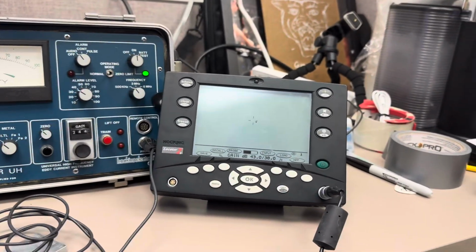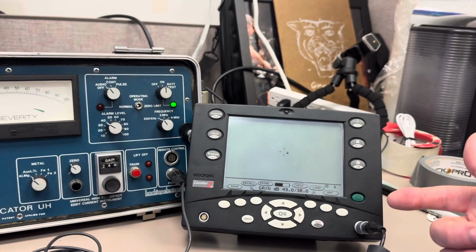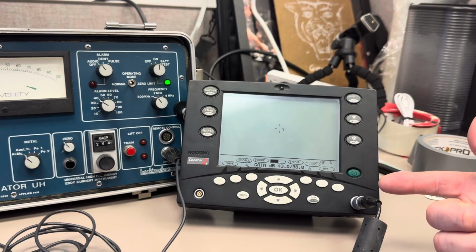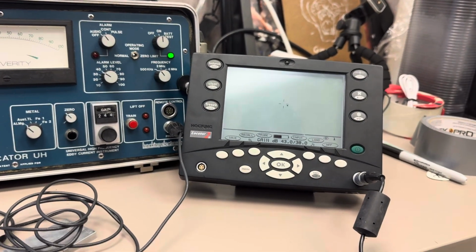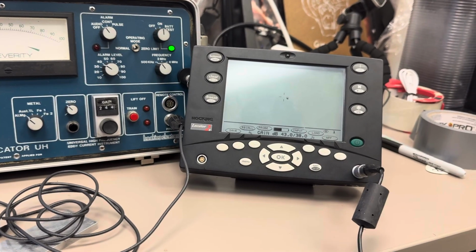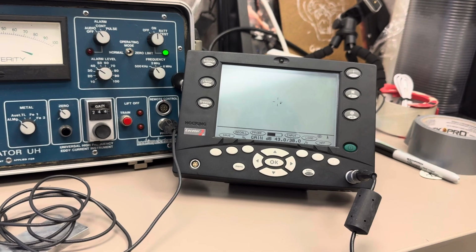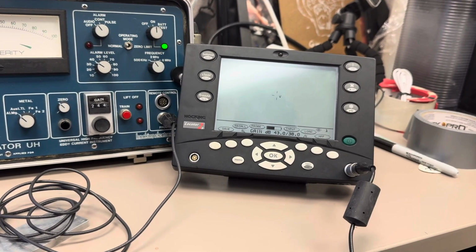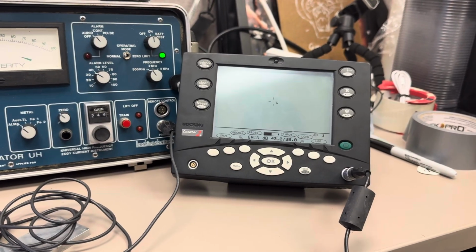Now, if you shift over to this one, this is the Locator 2S. This is not an impedance magnitude tester. This is an impedance plane instrument. What's different about the impedance plane instruments is not only do they give you the amount of change, usually expressed in volts per division, but it also gives you a timing or a phase change. So what does that look like?